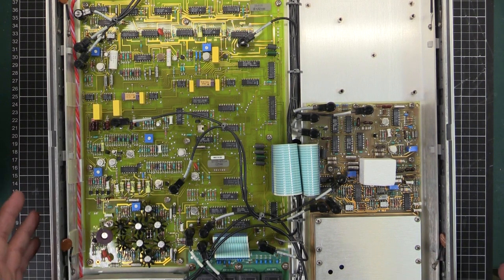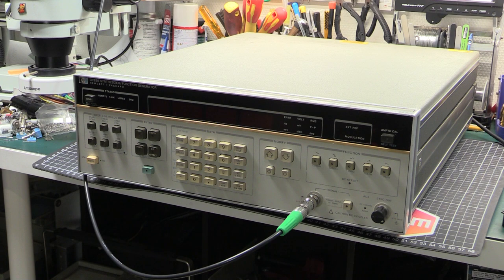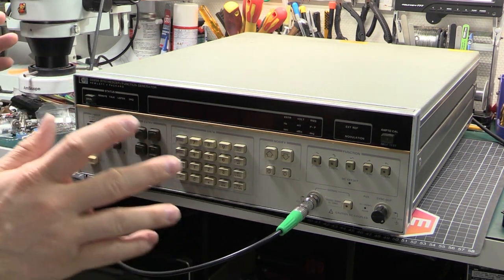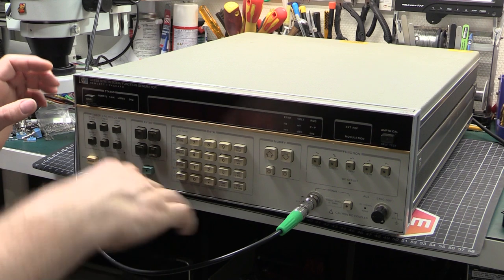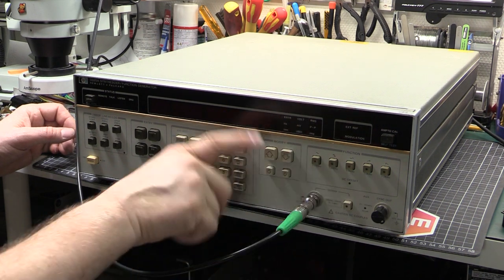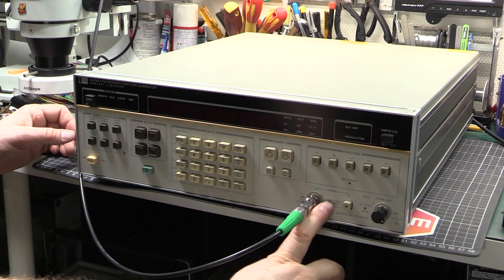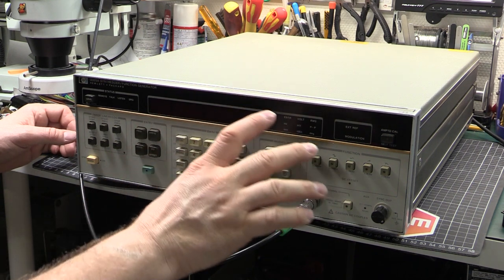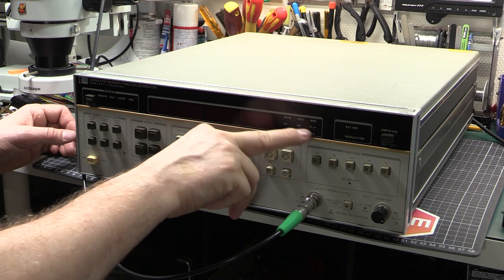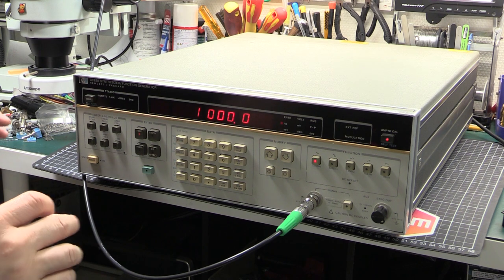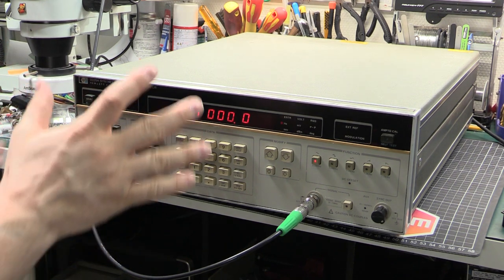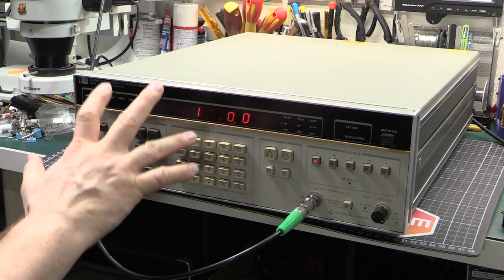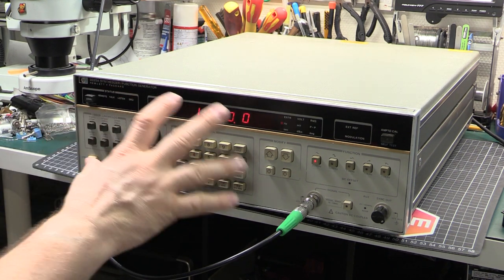Yeah. Apart from that. I think we're pretty much ready to put the lid on. And turn this on and see if it works. All right. We've got the thing together. Everything's installed. It's all hooked up. Ready to give it a smoke test. So I've got this hooked up to the scope. Off screen. I'll put some screenshots up. So you can see what's going on. As we work our way through. For the non Option 02 test. The non high voltage test. I've got a 50 ohm terminator here. I'll take that out when we do the high voltage test. Because that's only good for 40 milliamp output. So that's going to make it do some weird stuff. But yeah. So we need the 50 ohm terminator. When we're doing the normal test. Without the options. I'll read the peak to peak values properly. So. Let's turn it on. See what happens. Fan is fanning. Screen is screening. No smoke. No sparks. Fantastic. That's a good sign. So let's give it a test. In the normal mode. Without the high voltage option operating to start with. So we can see what's going on. Make sure everything's working first. So we're at a thousand hertz. One kilohertz. With a sine wave. The amplitude. So one millivolt now. Let's turn up to five volts.